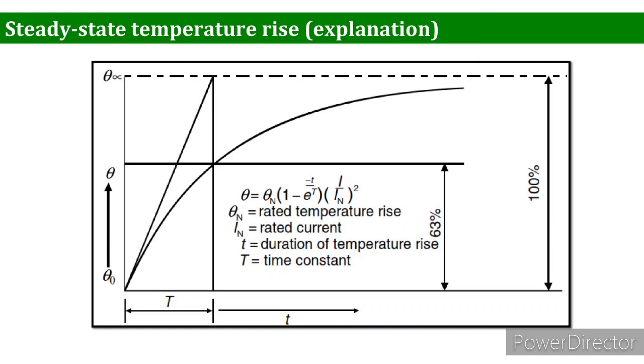So excessive thermal stressing of any appreciable duration must be avoided if the life of the insulation is not to be shortened. So it needs to be a point of care that we have to protect the winding or avoid any stress on the motor. Like you can see in the graph, under steady state conditions, the temperature of the motor will rise exponentially due to the dissipation of the heat to the environment.